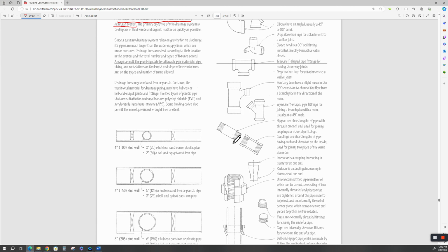These are couplings. They couple along our nipples. This is a nipple. It's a short piece of threaded pipe. If it's threaded piping, it's going to be NPT, National Pipe Thread. They have special dies to cut these because these threads are on a taper. This isn't a straight cut, single point cut like you would on a metal lathe. These national pipe threads, or national pipe taper, have a tapered thread on them. Okay, they're tapered. And I've got a whole 5-gallon bucket of pipe threads and threading tools that I've collected over the years out there for doing this.